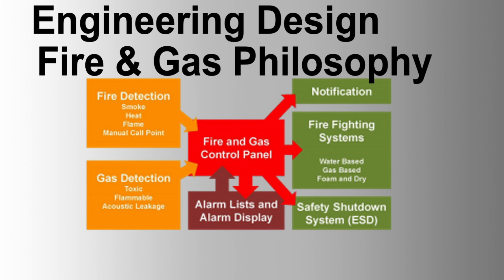Alarm functions. Alarm assessment and rationalization should be performed during detailed engineering. The fire and gas system acquires data from field devices, generates normal alarm conditions, and detects first-up alarms. Inputs should be time-stamped independently of the controller scan time, ensuring accurate sequence of events reporting.